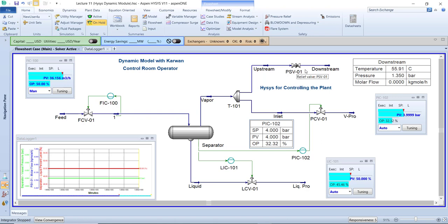If you're walking in the field inside a refinery or gas processing plant and a PSV pops up, you can hear it immediately because of its big sound. It creates a problem for your process because you lose a huge amount of vapor going to the flare, and sometimes the flare can't handle that huge amount. For that reason, you must protect your system and equipment first by monitoring your equipment and plant, and then if you get any alarm, directly check it. Please remember: check and monitor the plant all the time, and follow every alarm to take action and protect your equipment.